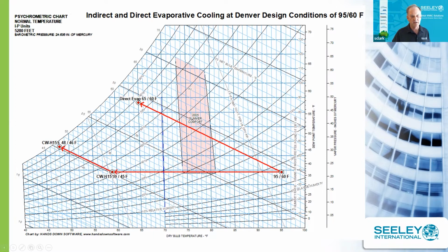Then on some of our units, we have what we call a super cool option, where we can follow the wet bulb line up. In this case, we're going down to about 48 degrees with that unit. These super cool units have a direct evaporative pad, which can be cycled on and off. So you can have indirect evaporative cooling down to this point, and cycle that on and off as necessary.